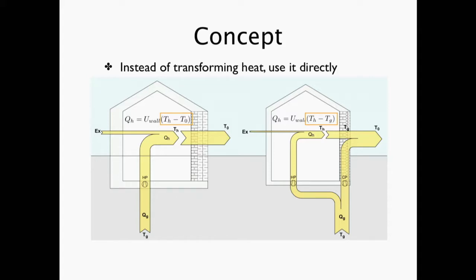So we said, why don't we play with that temperature? We can take some of that same really good ground temperature, which in general is about 55 degrees. It's not warm enough to directly heat the building, which is why the heat pump is needed—you still have to augment the temperature a little bit—but it's still much warmer than outside in winter when it's 0 degrees out.